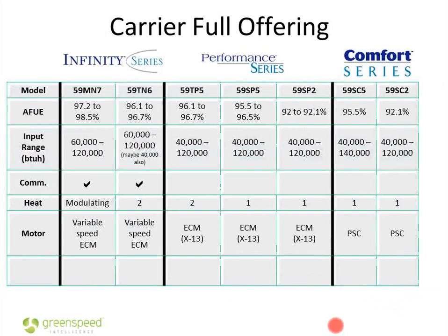Looking at the Carrier side, it's very similar, as you might expect. The Comfort Series has a 92 and a 95% model. Both are single-stage, and both use PSC blowers. The Performance Series has the 95% plus, which should really be called 96 because all the sizes hit 96% now, with 2-stage gas heat and an ECM motor. There's a 95% with single-stage heat and an ECM motor, and the new 92% single-stage ECM motor. So everything in the Performance Series is ECM, everything in the Comfort Series is a PSC basic efficiency motor, and everything in the Infinity Series is a variable speed motor.